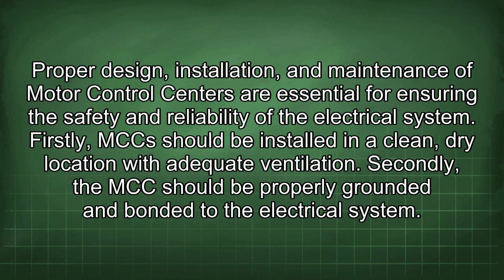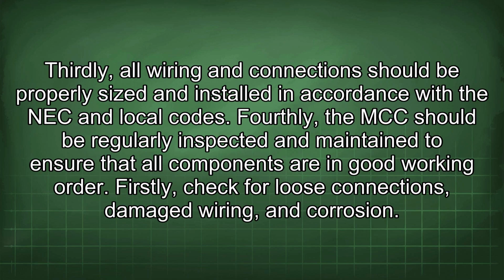Firstly, the MCC should be installed in a clean, dry location with adequate ventilation. Secondly, the MCC should be properly grounded and bonded to the electrical system. Thirdly, all wiring and connections should be properly sized and installed in accordance with the NEC and local codes. Fourthly, the MCC should be regularly inspected and maintained to ensure that all components are in good working order.